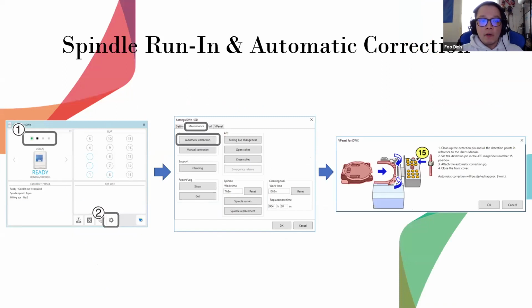Okay, now once that is all in together, we go to the same menu within the V panel, to the gear icon, to the maintenance, and now we're going to hit automatic correction. Okay, now in automatic correction, there are some parts of the mill that need to be cleaned. Okay, especially where the puck sits into the holder inside the mill, as well as the calibration plate itself and the pin.